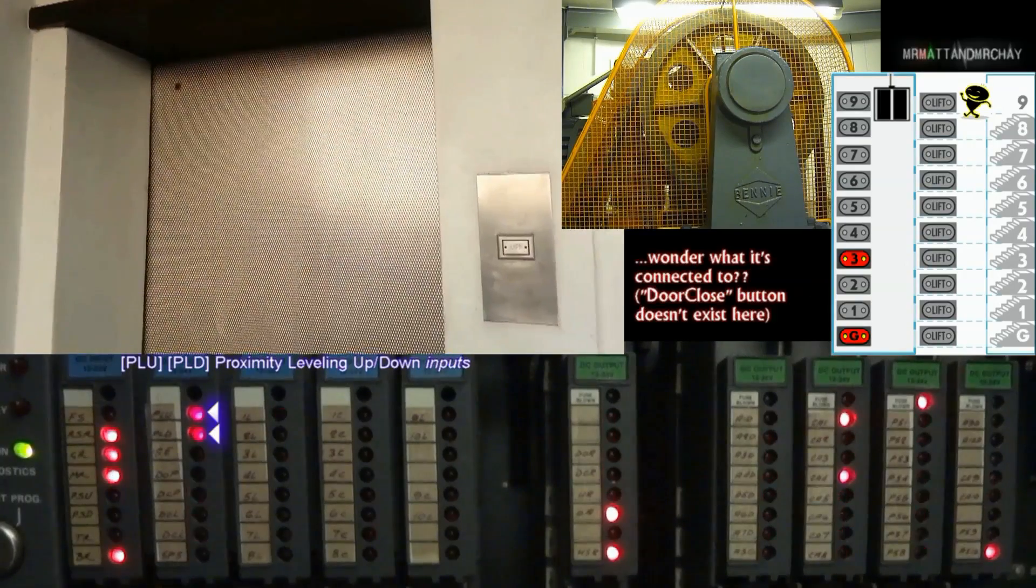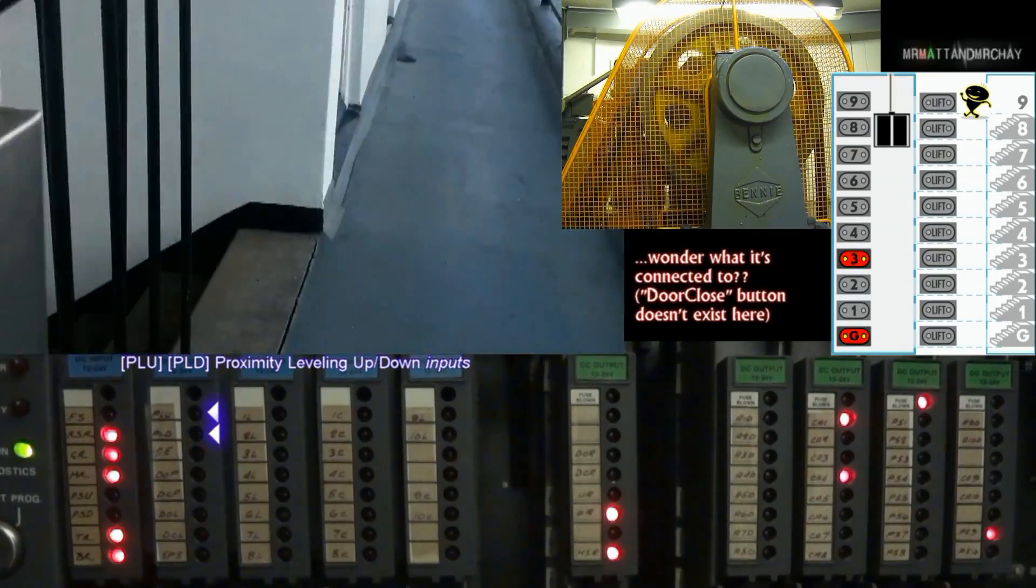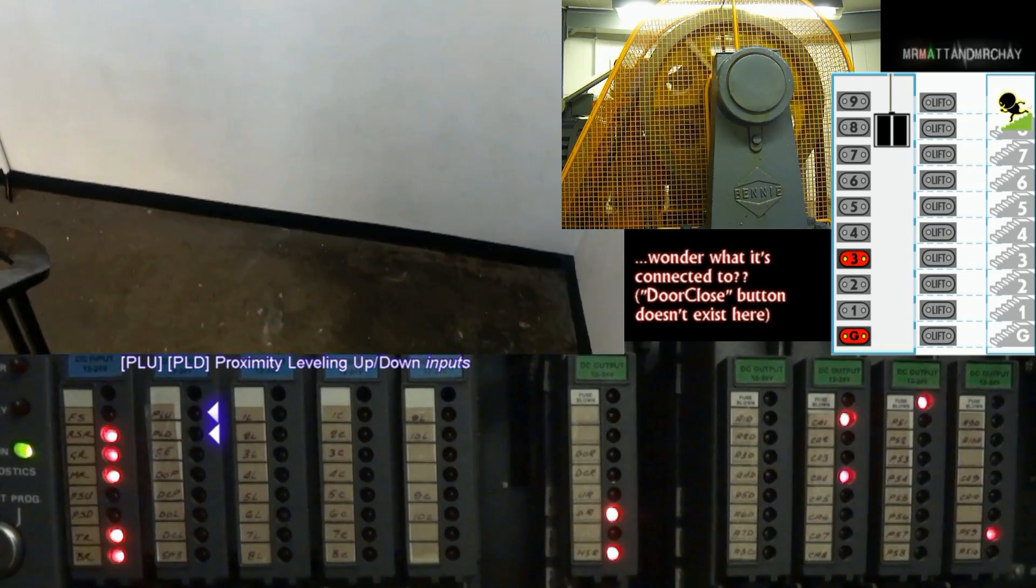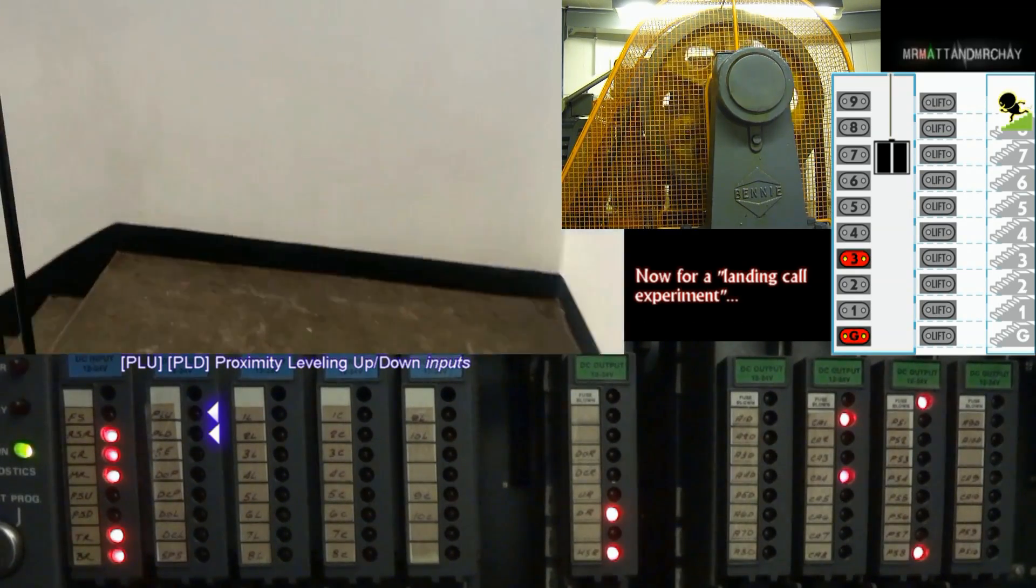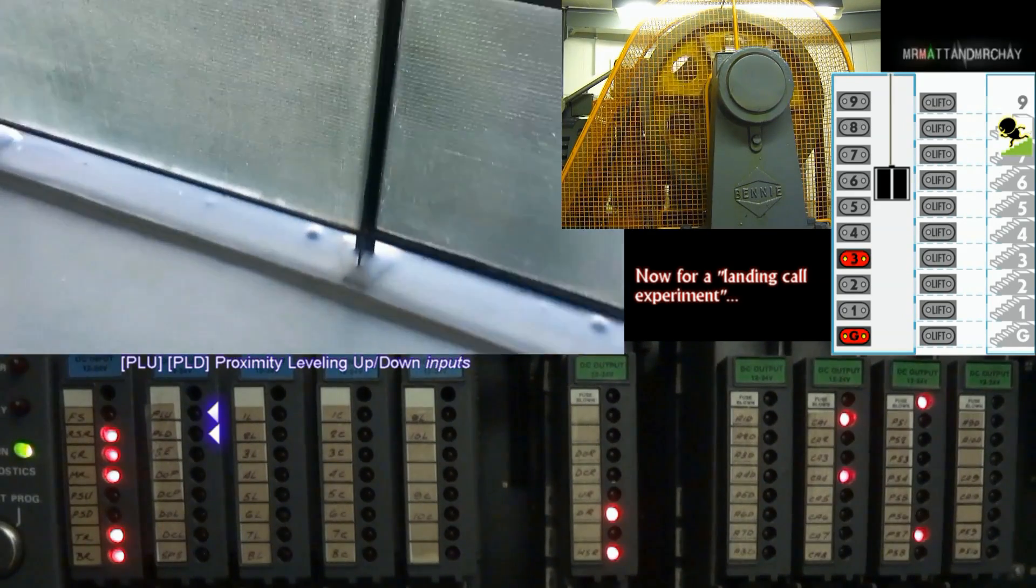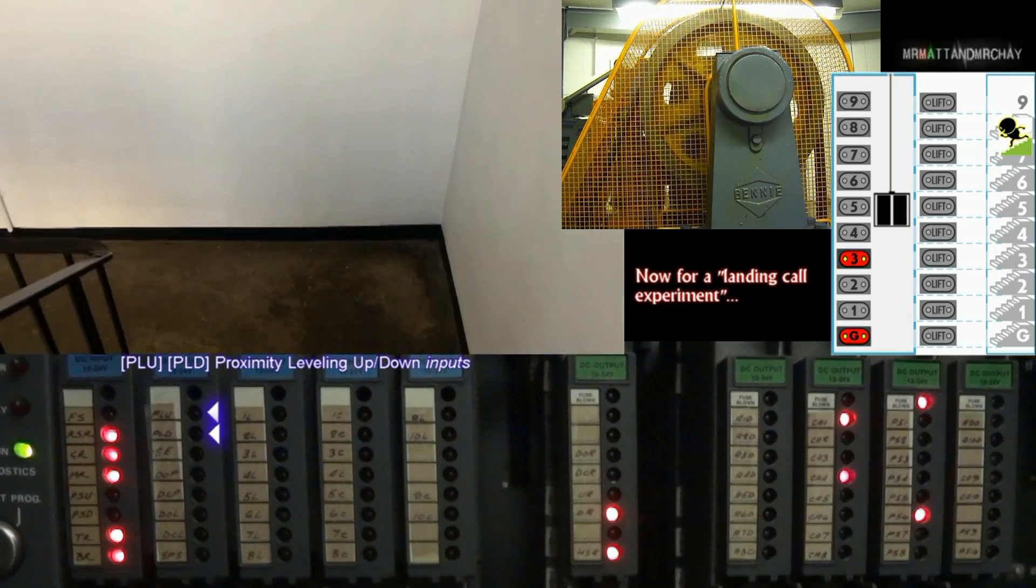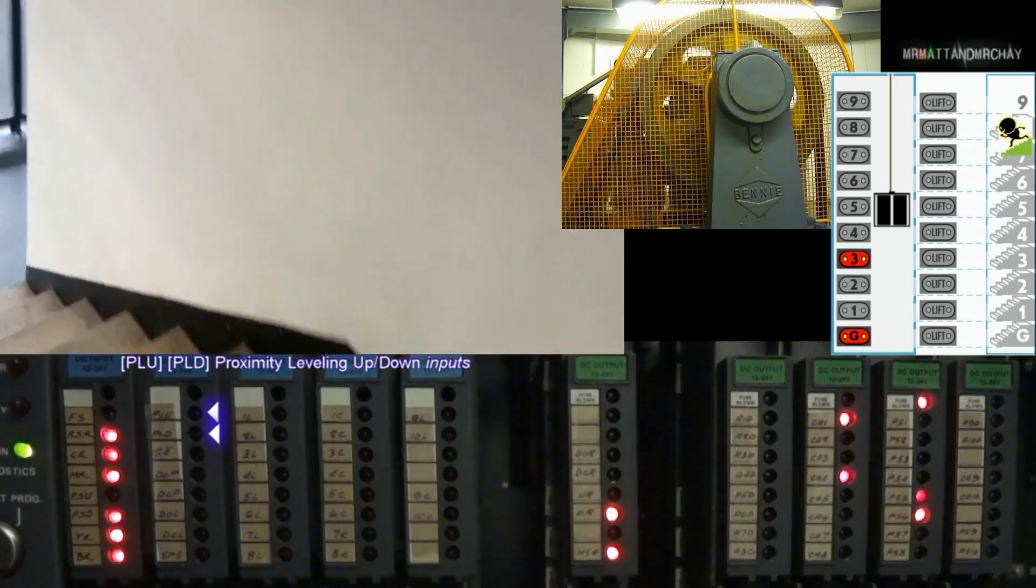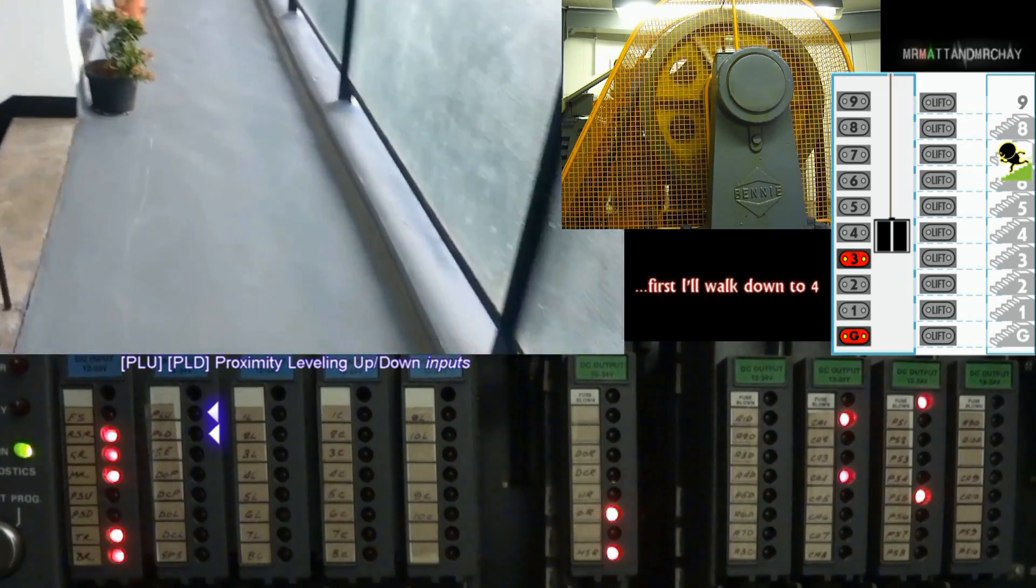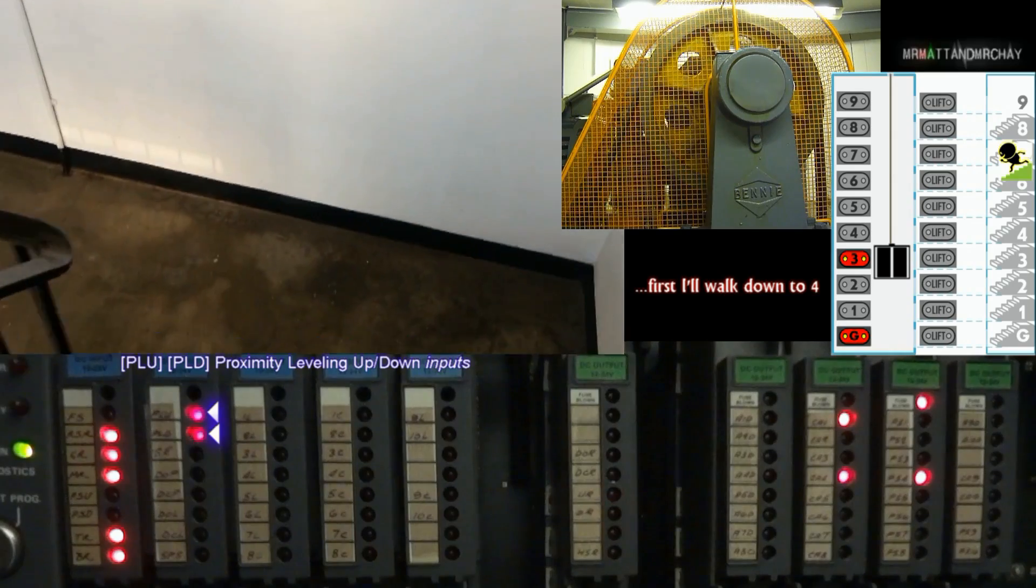PLU, car levelling inputs. The easiest way to describe this is to refer to magnets in the shaft that line up with each floor. The lift reads them and gives the stop signal to the controller. PLU is for levelling from an upwards direction, where PLD is for down. These overlap so that both PLU and PLD are both lit when the lift is level with the floor.